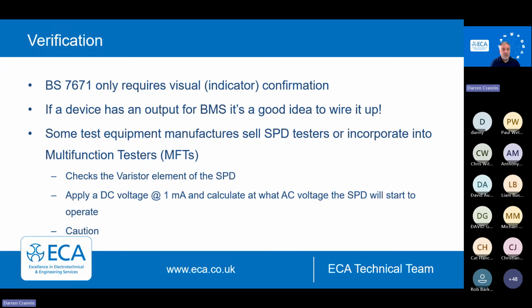There are testers on the market. Some are specialists, some are MFTs. For example, Metrel as an MFT do this. Sonel and other manufacturers produce SPD testers. Typically, and I can't speak for all manufacturers how they work, they check the varistor element of SPDs. Some may vary, and they typically apply DC voltage at 1 milliamp, and they look at when they're going to start conducting.